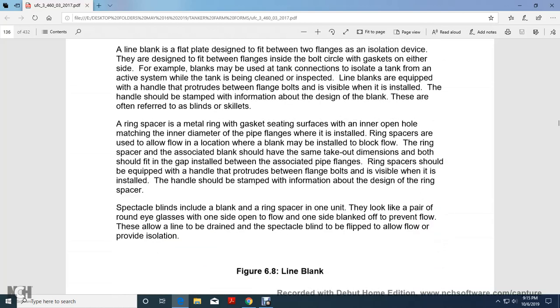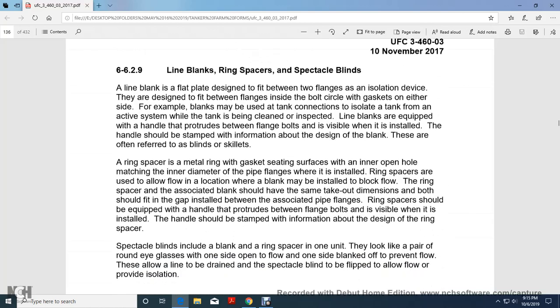Line blanks, ring spacers and spectacle blinds. A line blank is a flat plate designed to fit between two flanges for isolation, inside of the bolt circle, with a gasket on either side. For example, the blank may be placed at a tank connection to isolate the tank from any of the active system while the tank is being cleaned.